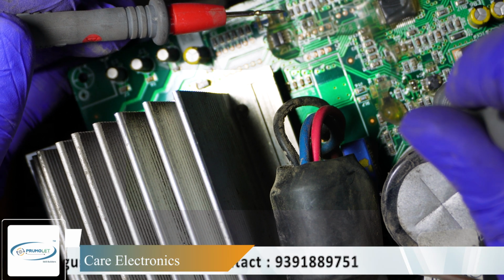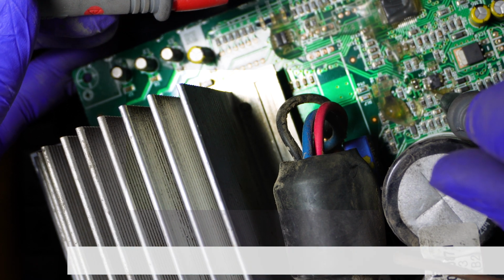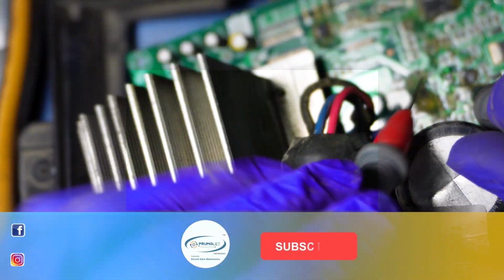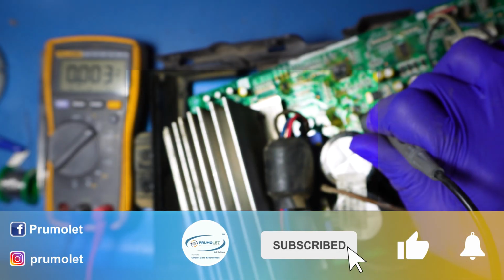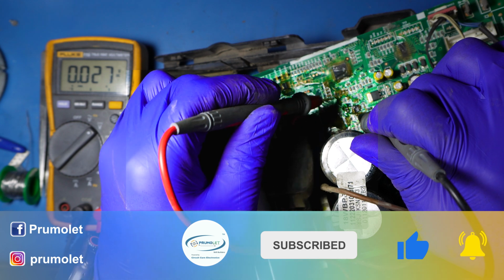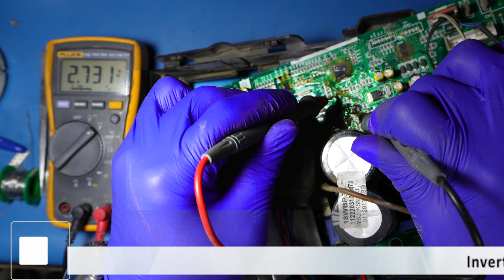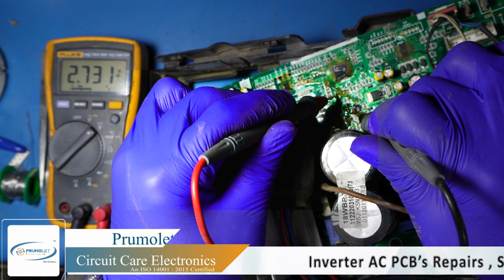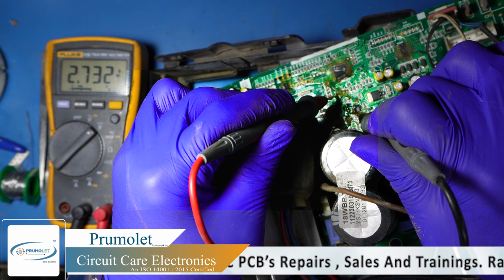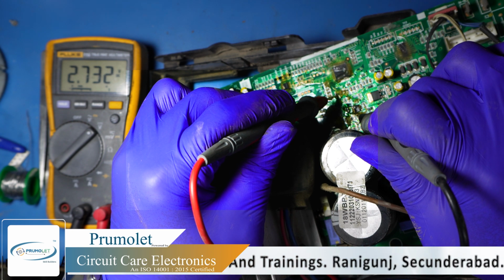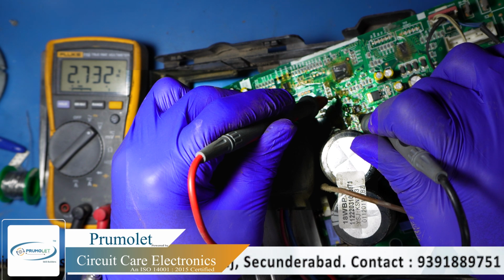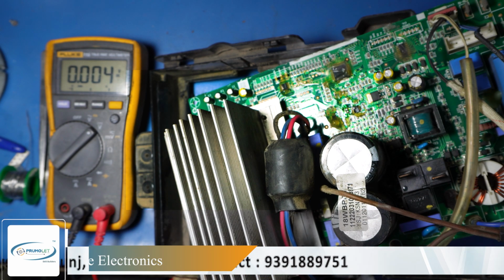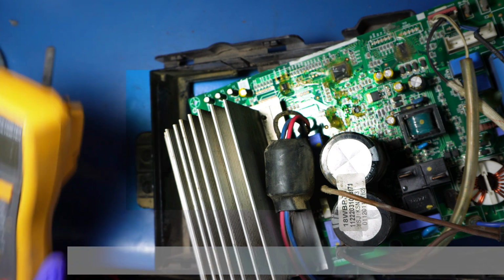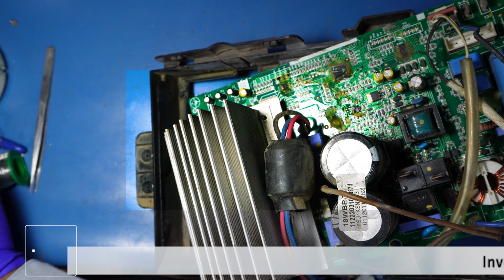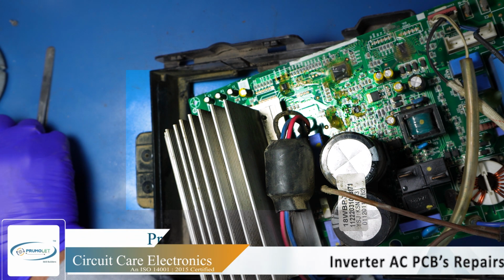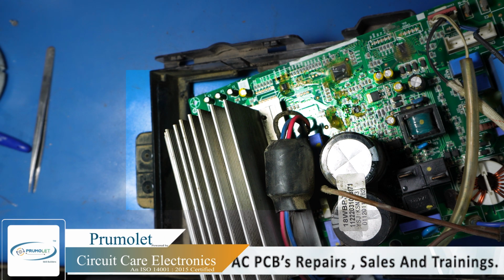here it is ground. You can take ground from anywhere. I'll show you the meter. See, now we are getting 2.7 volts. Previously we got 13.5 to 14 volts here. Now we are getting 2.7. So the problem is resolved. We'll do the load test once. If it runs well, everything will be good.